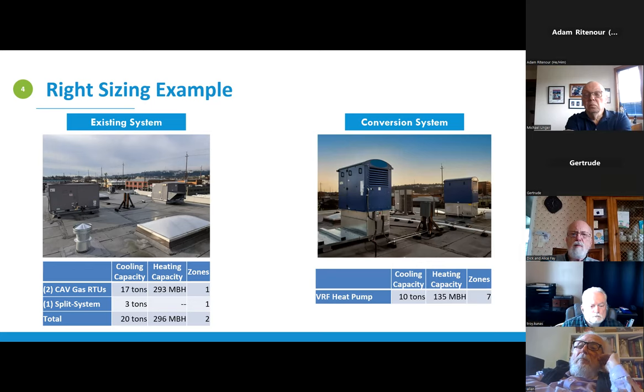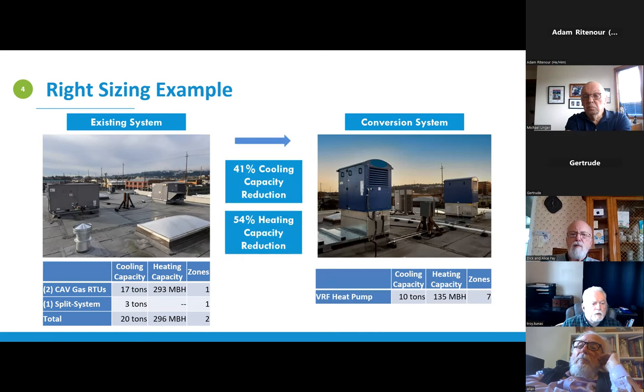And by doing so, we actually reduced our cooling capacity by 41% and our heating capacity by 54%. And that's what I mean by right sizing. With consideration to the ventilation units and the heat recovery or heat rejection on days of cooling, we sized our heating and cooling system to serve just the load from building envelope losses and a little bit of what's not recovered from the heat recovery ventilator.